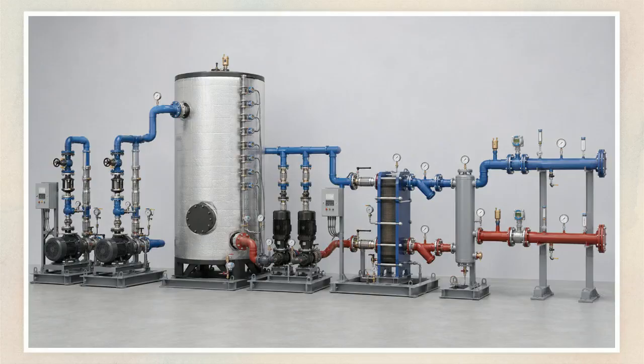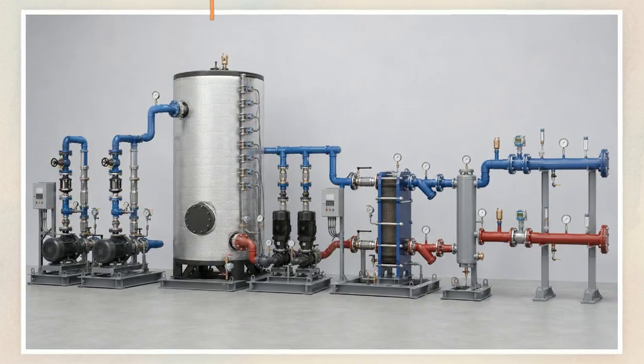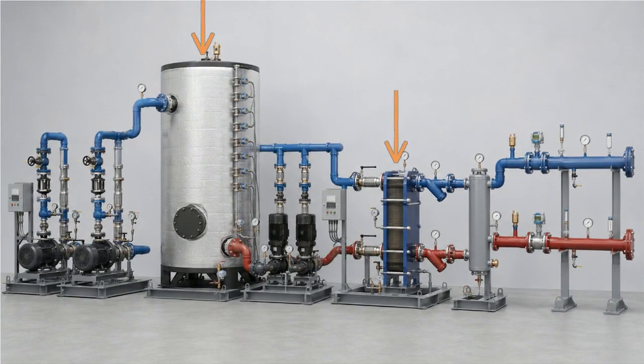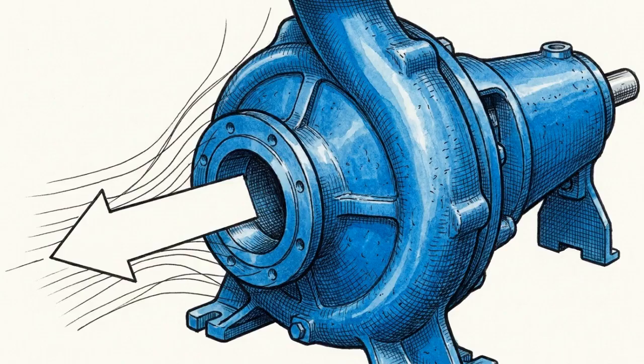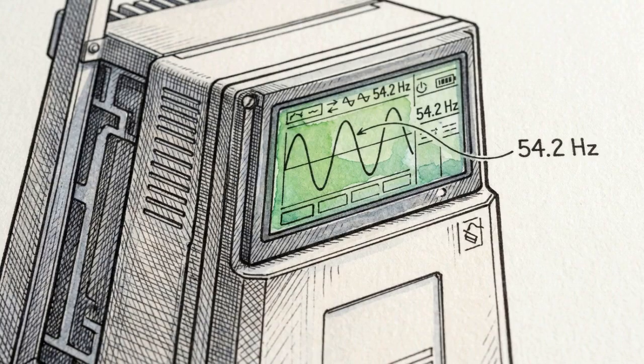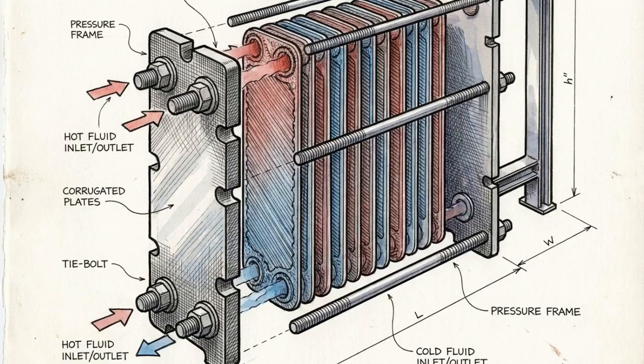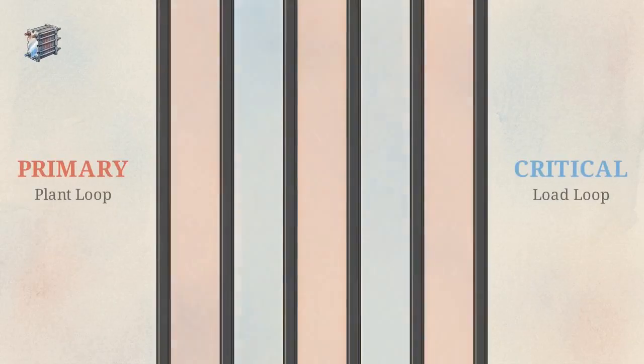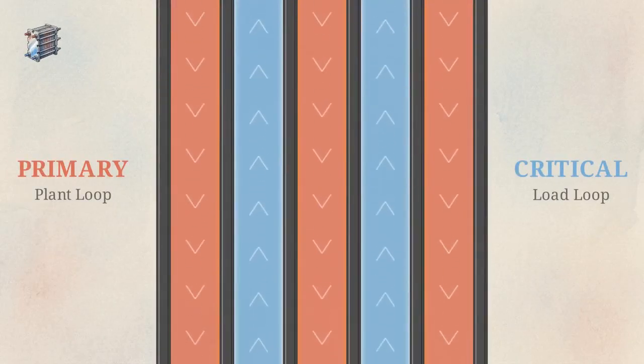Moving from the blueprint to the actual hardware skid, we can trace the complete thermal storage service path. The sequence begins at the charge pumps, moves through the insulated thermal energy storage tank, and arrives at the plate heat exchanger. The charge and discharge pumps push the water through this sequence. Because system resistance changes constantly, these pumps rely on variable speed drives and check valve isolation to maintain precise control over the flow. The plate heat exchangers and decouplers serve as the physical gatekeepers of the system. They enforce fluid separation and pressure boundaries between the primary plant and the critical load.